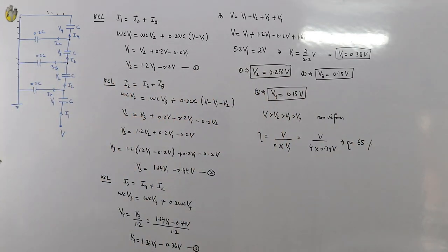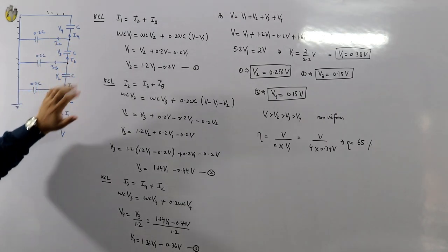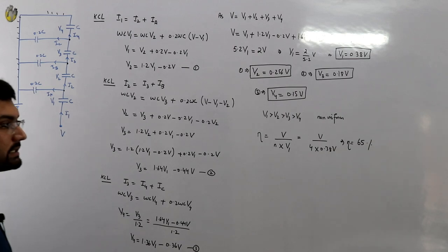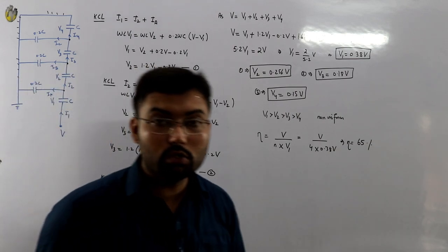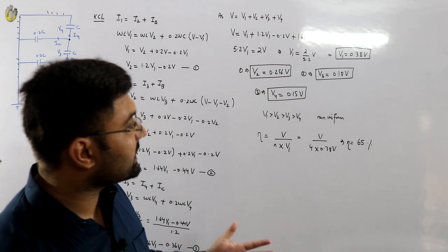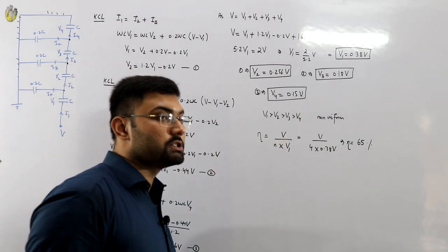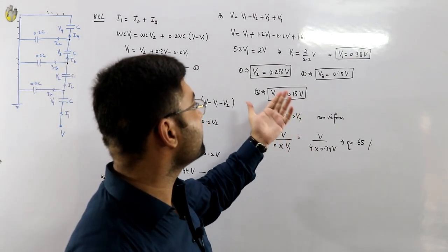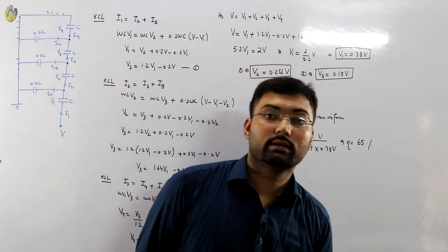Fine, yes. Now this is video number 1 where I have not used my guard ring. Let's say in the next video I use my guard ring and I check again for the improvement in the string efficiency and a little bit of uniformity in the string, in the voltages.